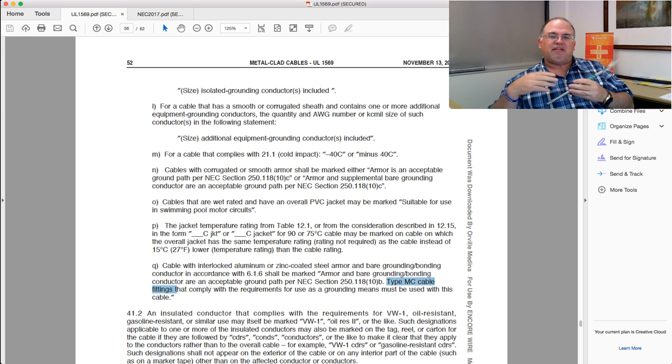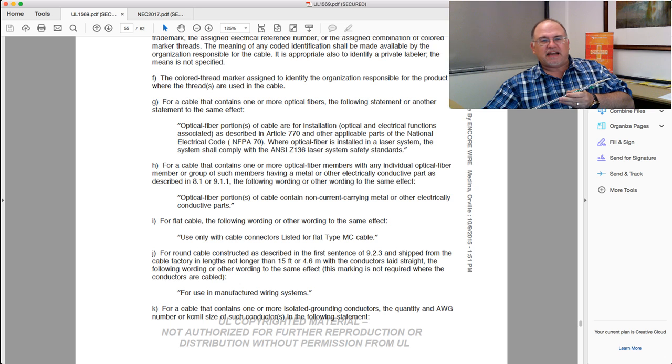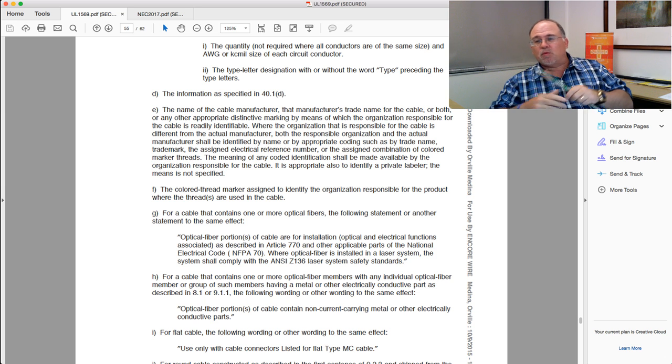None of which has to be placed on the cable. So when somebody says it has to be identified for its use, there's nothing in MC cable that requires it to be identified on the cable. The standard specifically allows for it to be on a label, a tag, or the reel. That's what it says. UL 1569 is the listing; the labeling requires the manufacturer's name and all of that information to be put on the label, tag, or reel itself — not on the actual cable.